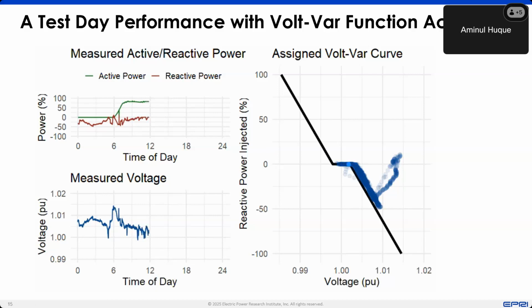But the main conclusion is that pretty much throughout the day, it was following the setting provided to it, with few exceptions where it was off from the target. And you can clearly see, voltage goes high, it is absorbing VAR; voltage goes low, it is injecting VAR. So it can provide the support in both directions.